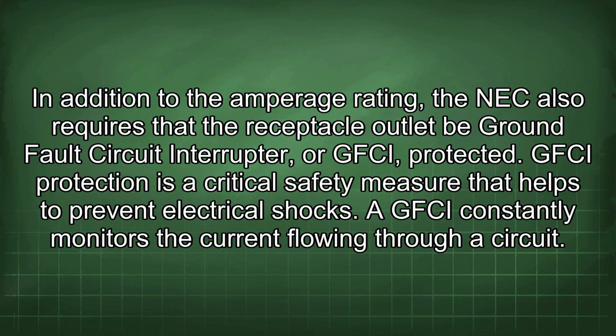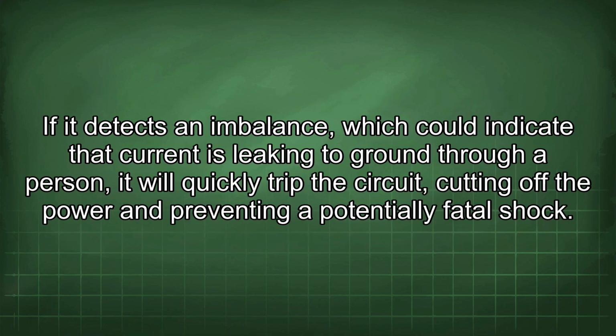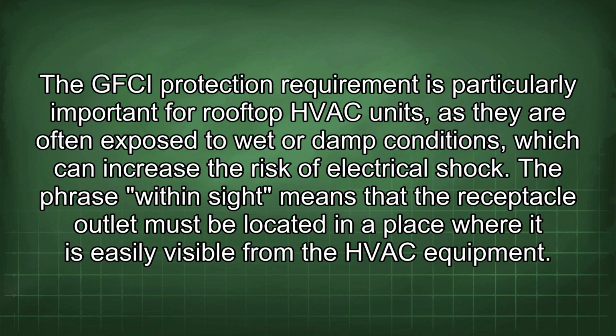In addition to the amperage rating, the NEC also requires that the receptacle outlet be ground fault circuit interrupter, or GFCI, protected. GFCI protection is a critical safety measure that helps to prevent electrical shocks. A GFCI constantly monitors the current flowing through a circuit. If it detects an imbalance which could indicate that current is leaking to ground through a person, it will quickly trip the circuit, cutting off the power and preventing a potentially fatal shock. The GFCI protection requirement is particularly important for rooftop HVAC units, as they are often exposed to wet or damp conditions which can increase the risk of electrical shock.